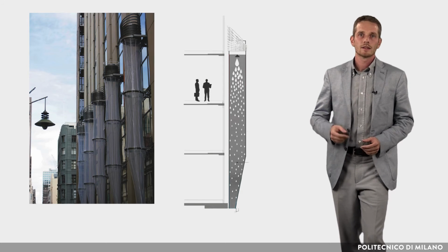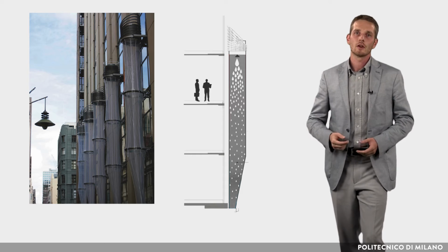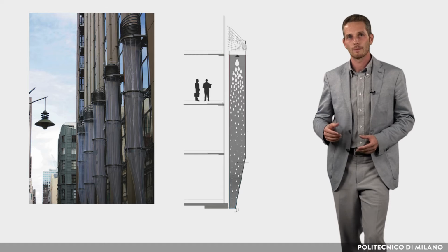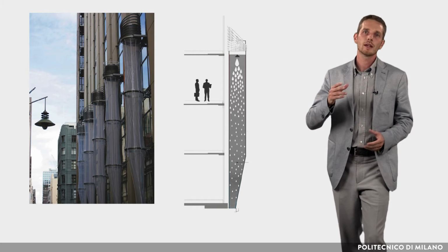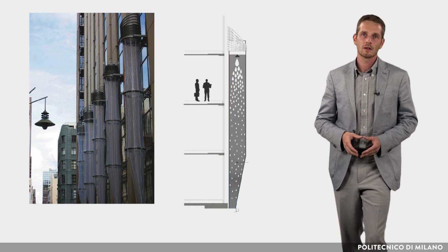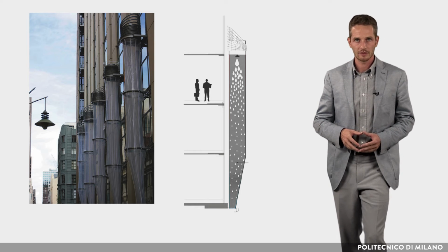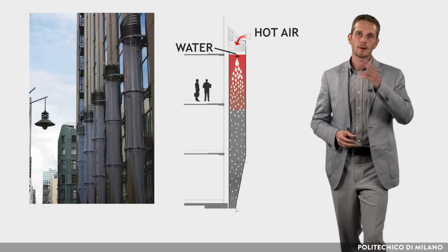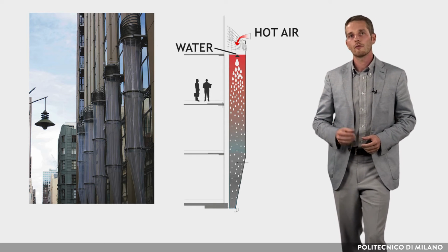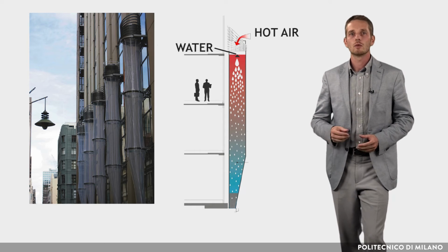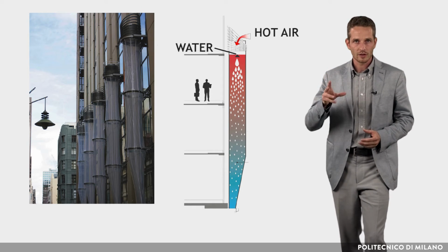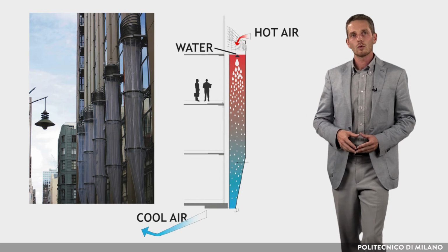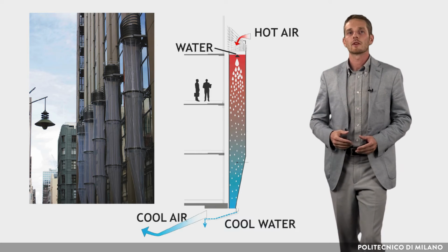In the second one, the showers along the southern facade of the building cool air for intake and use it in the ground floor. The showers are made from tubes of lightweight fabric 1.4 meters in diameter. As the water falls within the tower, it sucks in air from above. This air falls down the tower and it is cooled by evaporation from the shower of water. The cool air is supplied to the retail spaces and the cool water precools the water coming from the chilled ceiling panels.